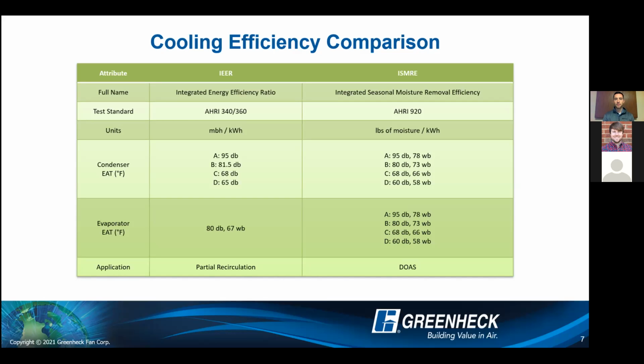So generally, if you see that on our type of equipment in the submittal package, or you hear any of the Holden guys talk about it, that is going to be for a true DOAS type system. So I'm going to jump all the way to the bottom of this table.